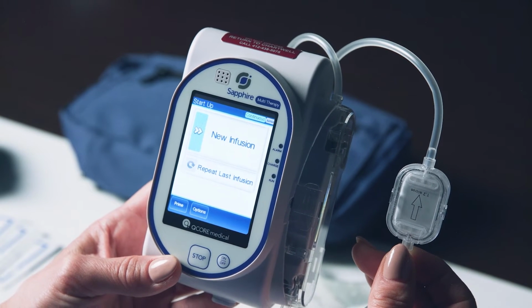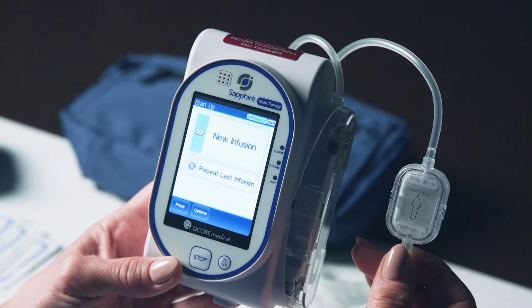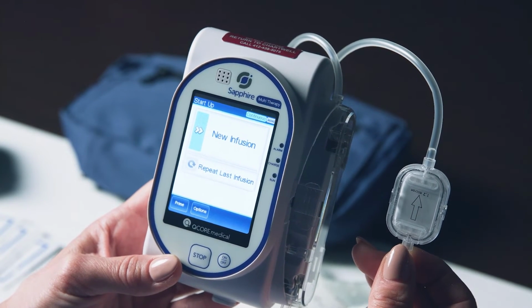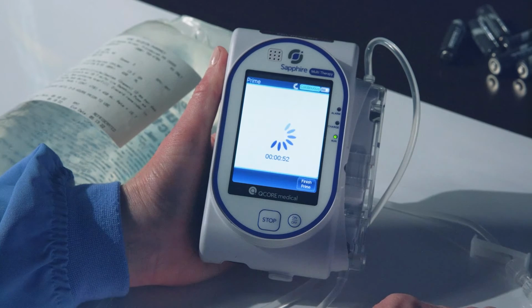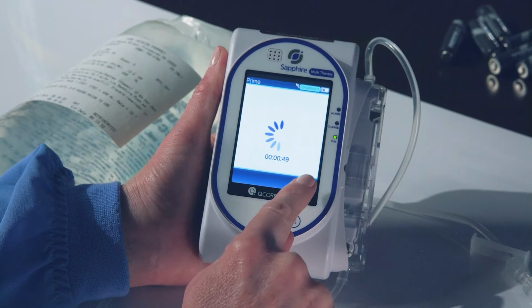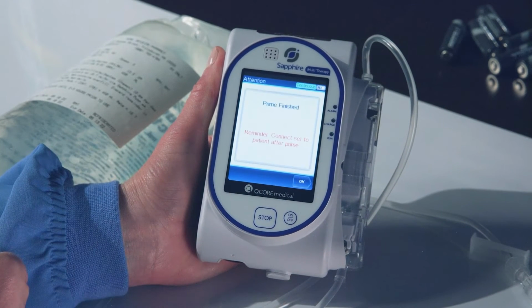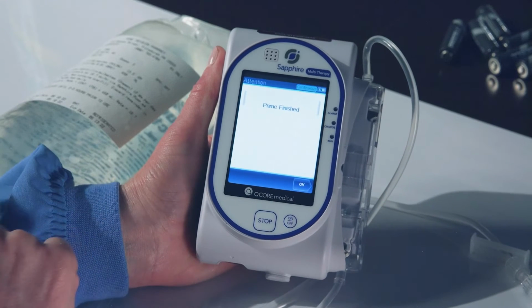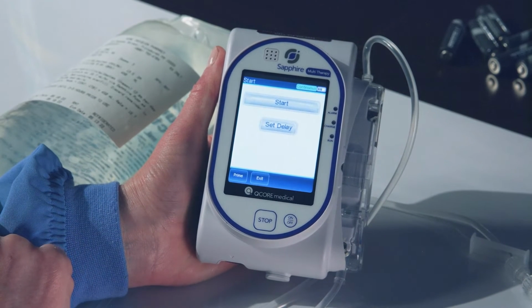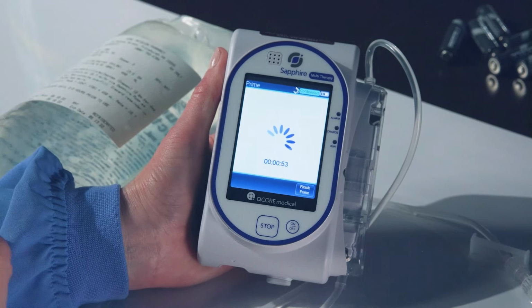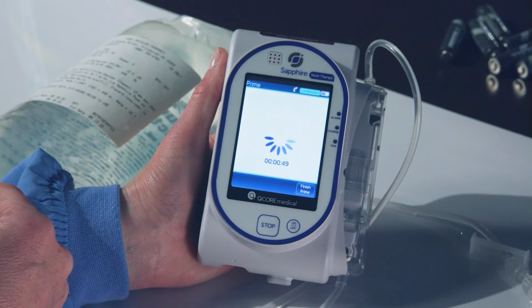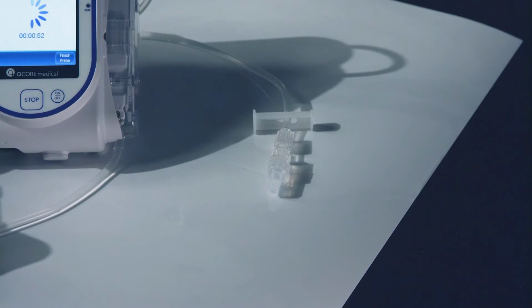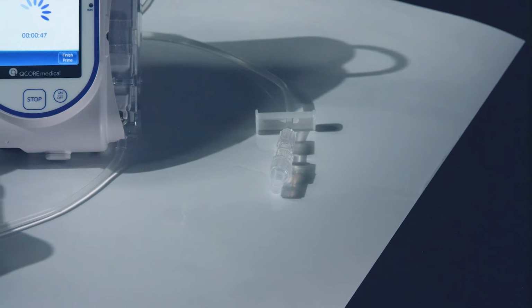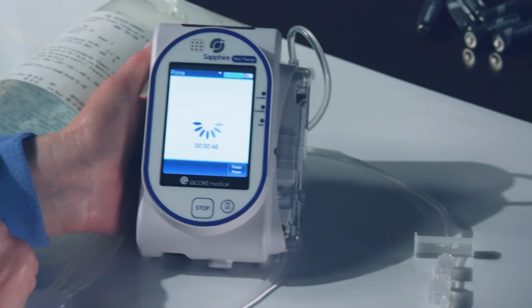The pump will automatically prime a preset amount of medication through your tubing. If the tubing is primed before the preset amount is reached, you can press Finish Prime and then OK. If not, once the preset volume is reached, press OK at the completion of the prime. When the tubing is filled with medication, priming is now complete. If not, you will need to press Prime again and repeat the process until the tubing is fully primed.